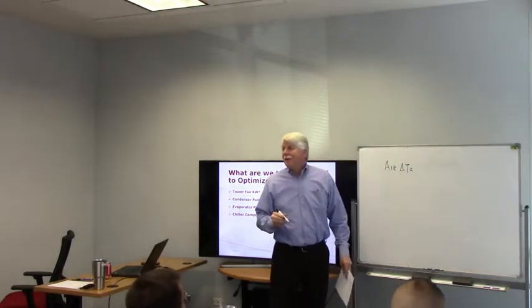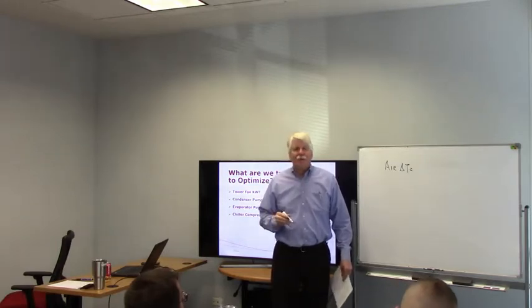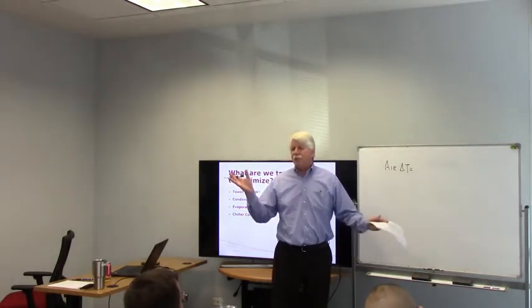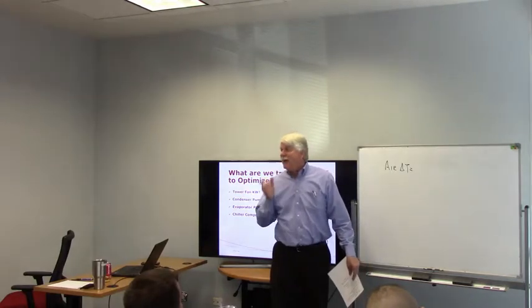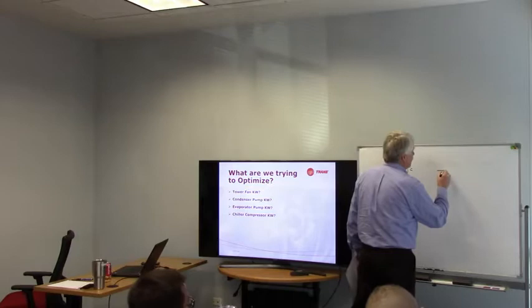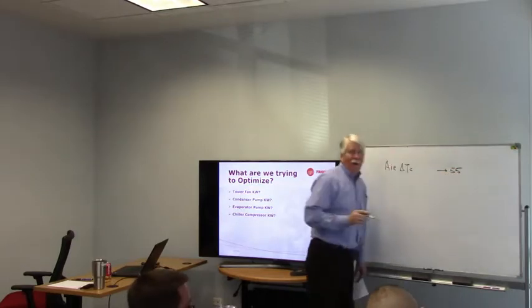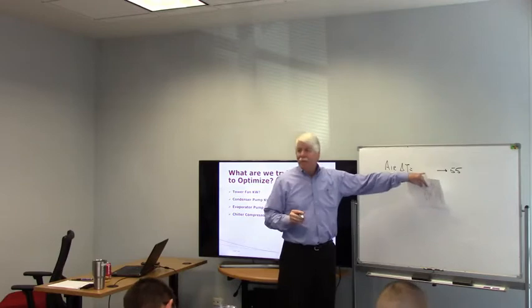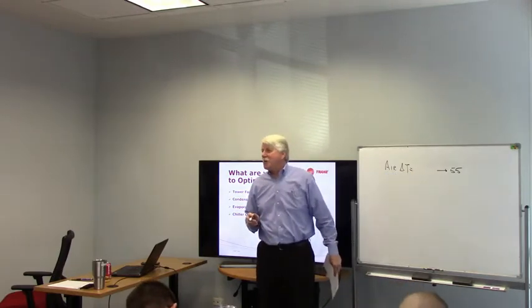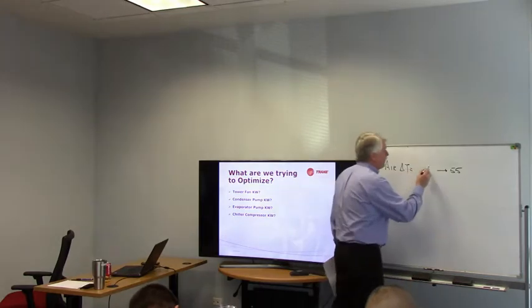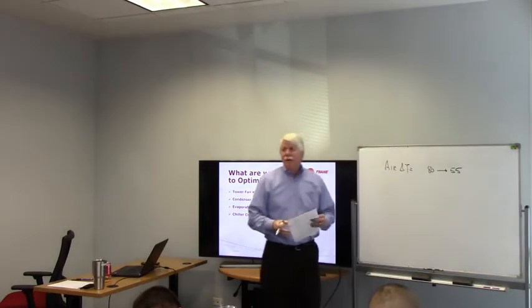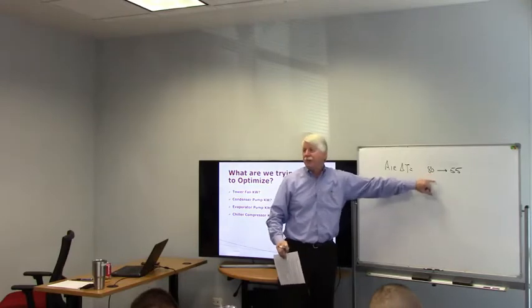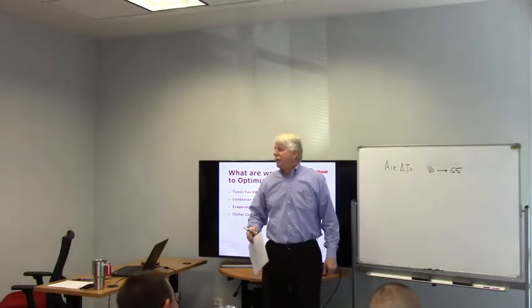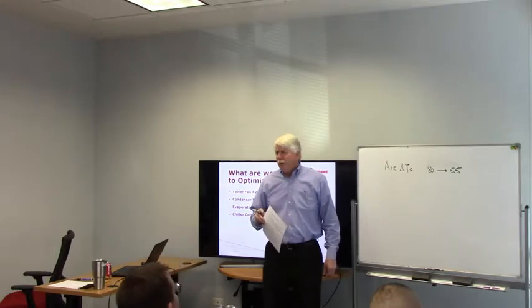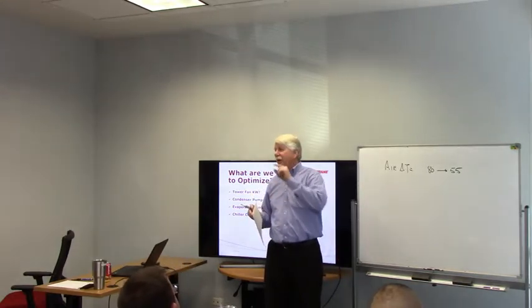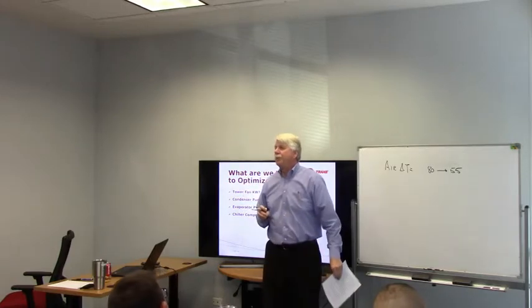Okay, let's talk about air delta T. Most systems, what temperature supply air do we provide? 55. I gave you the answer to this. In Chicago, what's our normal mixed air temperature? 80. 80, okay? So, for most systems, this is what we would expect to normally see on a cooling coil, all right? Now, I think almost everybody in this room has been involved in a job, actually two of them.